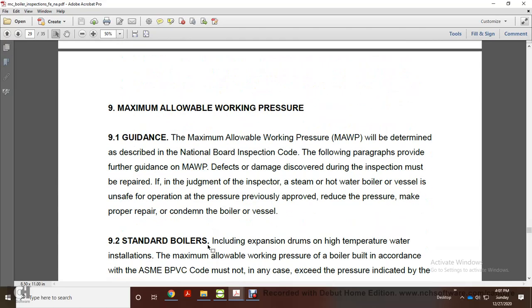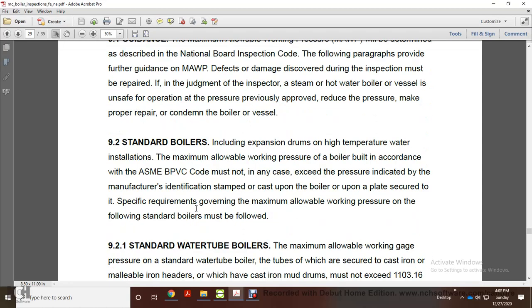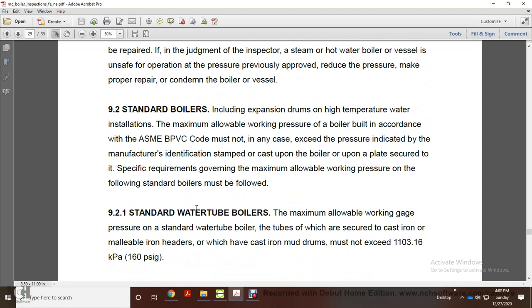Alright, 9. Maximum allowable working pressure guidance. The maximum allowable working pressure is determined in accordance with the National Board Inspection Code. The following paragraphs provide the maximum allowable working pressure. Any defect or damage discovered during the inspection must be repaired. If, in the judgment of the inspector, the steam or hot water boiler vessel is unsafe for the operating pressure previously approved, reduce the pressure, make the proper repair, or condemn the boiler vessel.